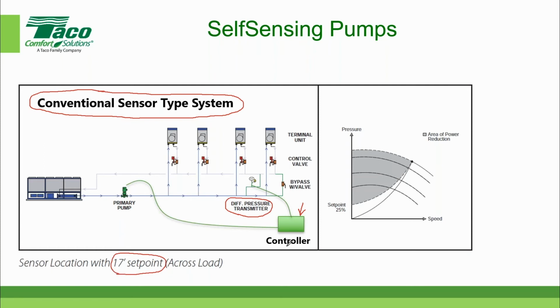And then what I'm going to do, since I'm the controller, I'm going to send a hardwired signal to the variable speed drive. And it works like the following. It says, okay, if I have a 17-foot set point, as these valves begin to open, the pressure differential is going to drop. The controller is going to say, hey, wait a minute, I'm not maintaining my 17 feet, so I need to speed up the pump by sending a hardwired signal to the variable speed drive on the pump, and that'll speed the pump up, and I'll get back to the pressure that I'm looking for.